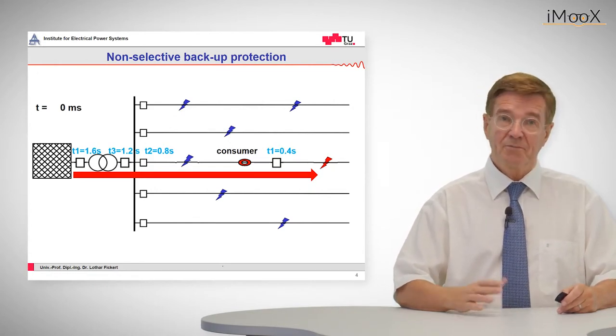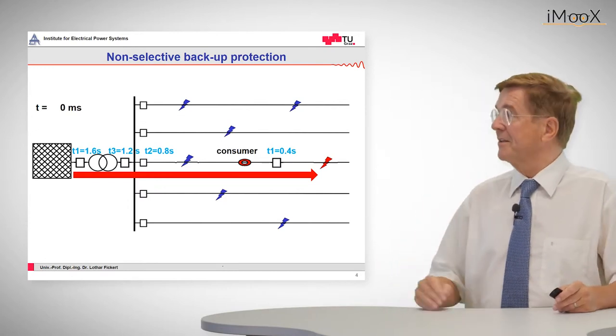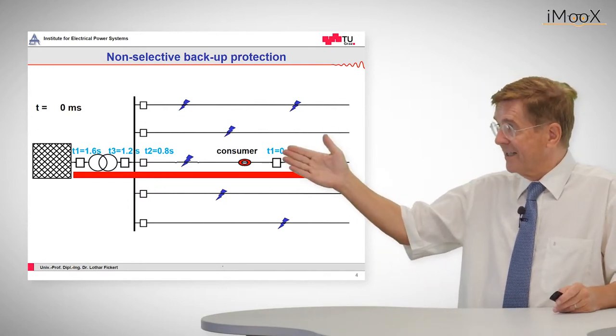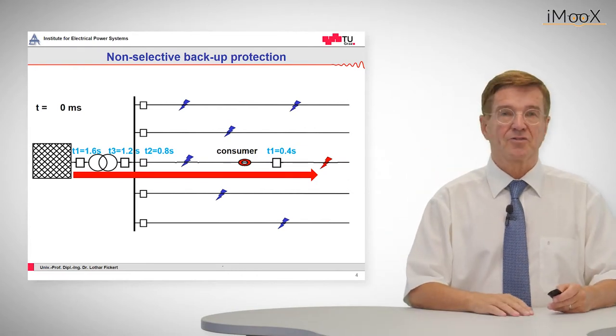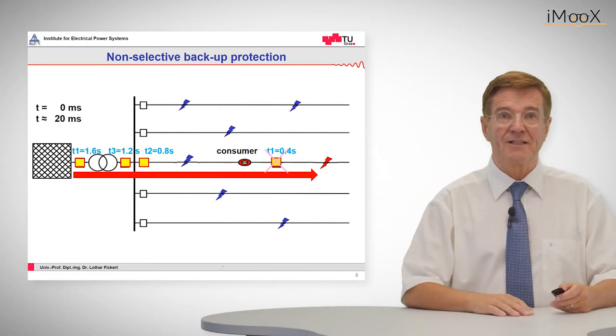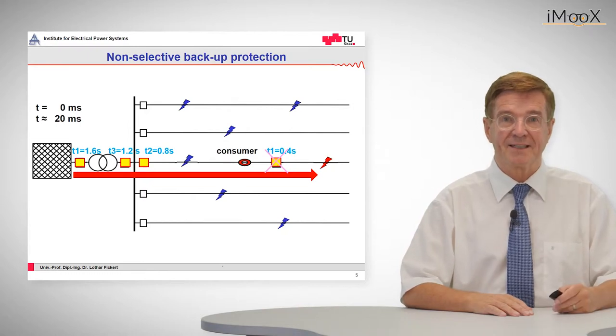So in this previous chapter, we saw that when there is a fault at the end of this line, indicated by this red flash, the current goes through all protection relays. All these relays will pick up as is indicated in yellow.